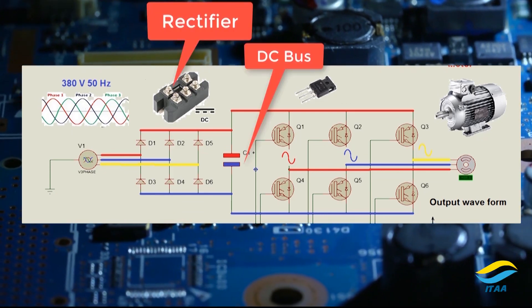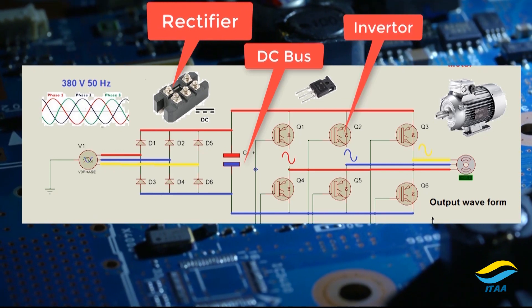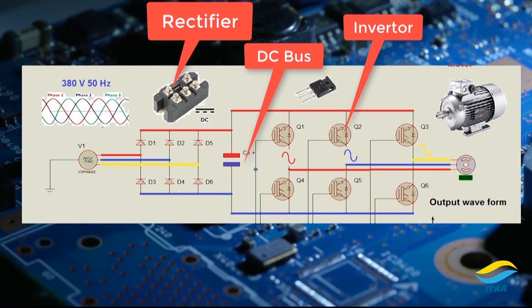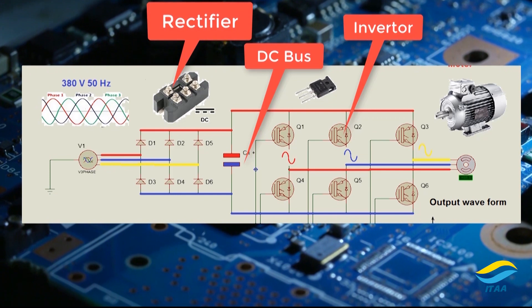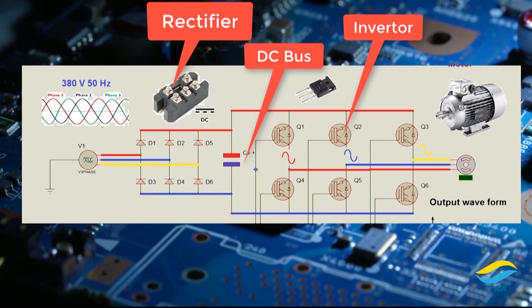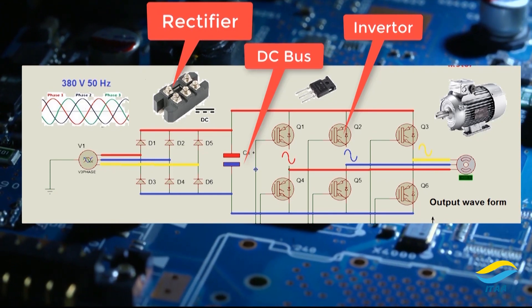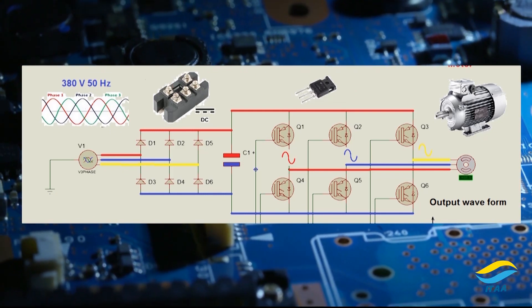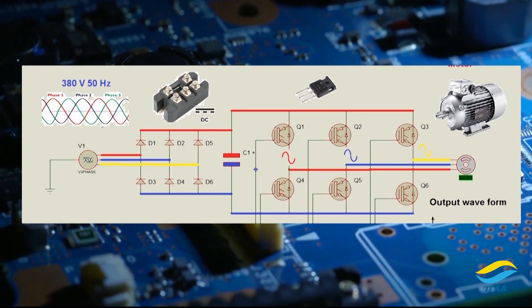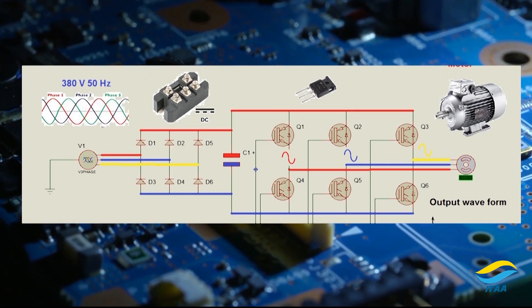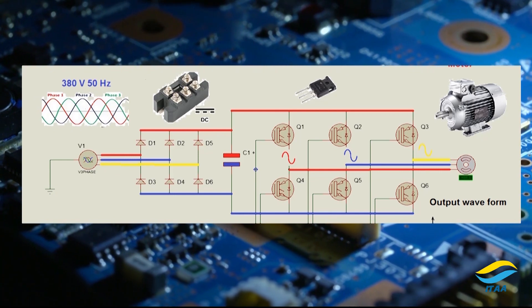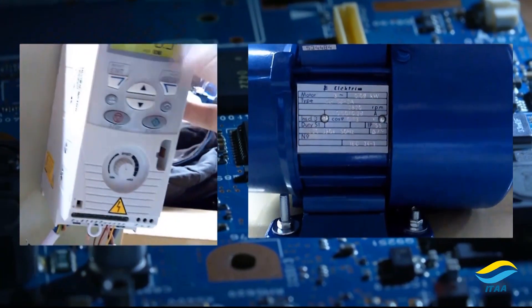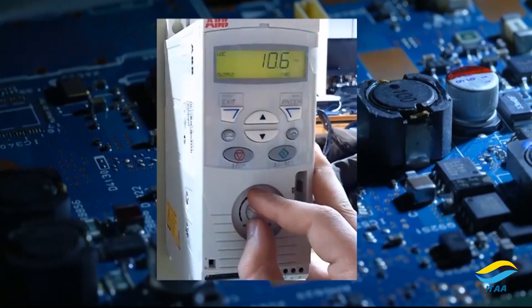In short, we have three elements: first is the rectifier, then the DC bus system, and then the inverter. In the rectification process, we have six diodes whose role is to convert the AC signal to DC. Since this DC signal is choppy, we use a capacitor in the DC bus to clean it. The clean signal is then passed through the inverter, where IGBTs or transistors convert it back to AC, ready for the motor to use.